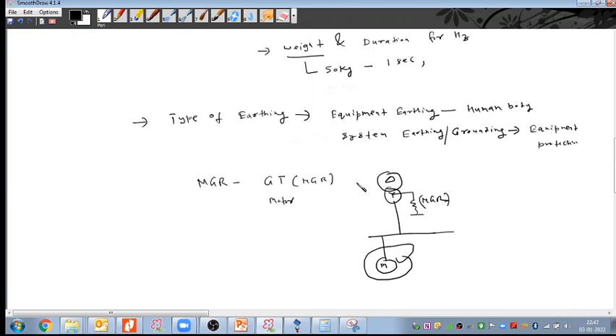As a design engineer, you should go for NGR in these two places. For other cases it is not mandatory, because if there is no rotating machine, there is no winding, no core, and no insulation of the core. So what will get damaged? In that case we can avoid the NGR, but in this case we cannot avoid it.